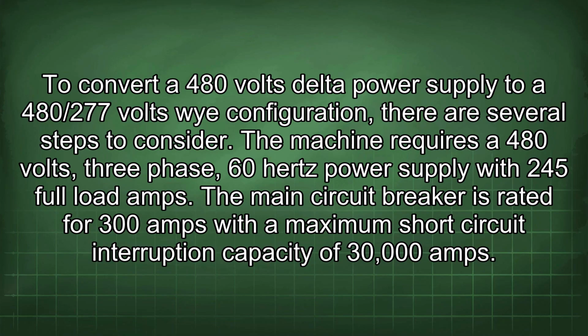To convert a 480 volts delta power supply to a 480/277 volts Y configuration, there are several steps to consider. The machine requires a 480 volts, 3-phase, 60 Hz power supply with 245 full load amps. The main circuit breaker is rated for 300 amps with a maximum short circuit interruption capacity of 30,000 amps.